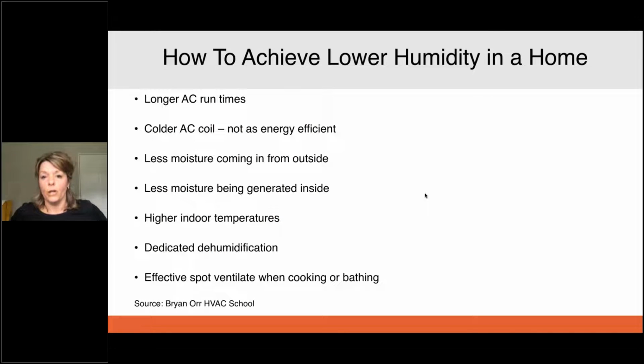So how do we achieve lower humidity at home? And this is the other part of Bryan Orr's article. We need longer AC run times. So we might need to downsize that AC system to get it to run a little bit longer, work a little bit harder. Colder AC coils. So your really energy efficient AC systems typically have a higher coil temp in order to get to that sensible quickly and not use as much energy than an older system, or a system that's been adjusted to run a colder AC coil and maybe run a little bit longer.